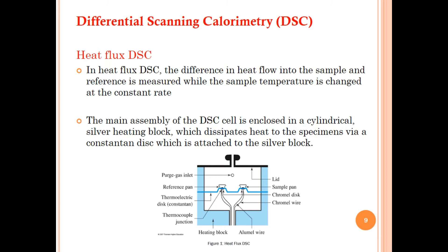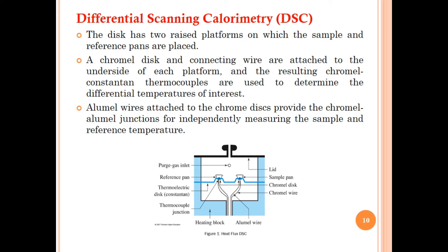In heat flux DSC, the difference in heat flow into the sample and the reference is measured while the sample temperature is changed at a constant rate fixed in the temperature program. The main assembly of the DSC cell is enclosed in a cylindrical silver heating block, which dissipates heat to the specimen via a constantan disk attached to the silver block. The disk has two raised platforms on which the sample and reference pans are placed.